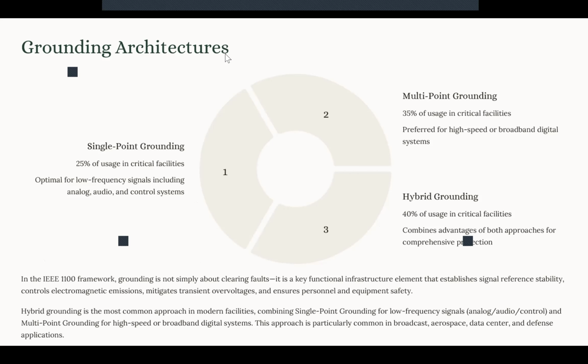We already talked about the grounding architecture. We said we have a single point grounding architecture, a multi-point grounding architecture, and a hybrid grounding architecture, and we select those based on the application of our grounding system. So in a very small network, we can use single point grounding. If we have medium sensitive, not highly sensitive, or large networks, we need to have multi-point grounding.